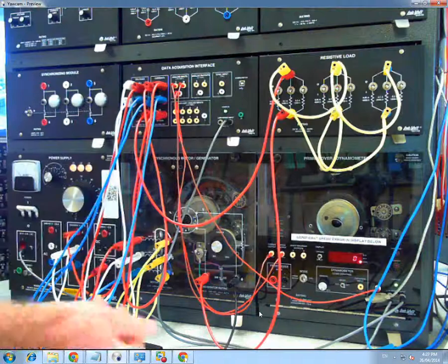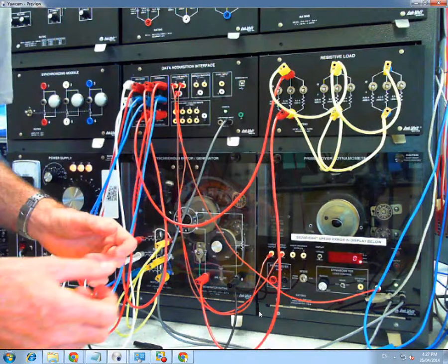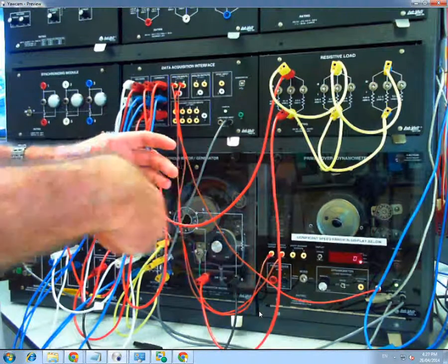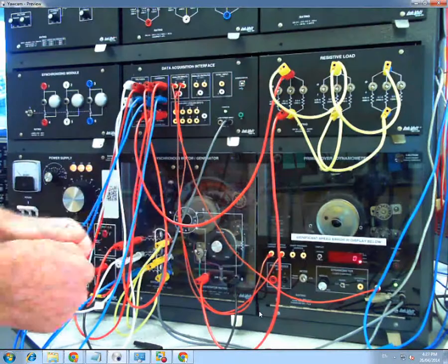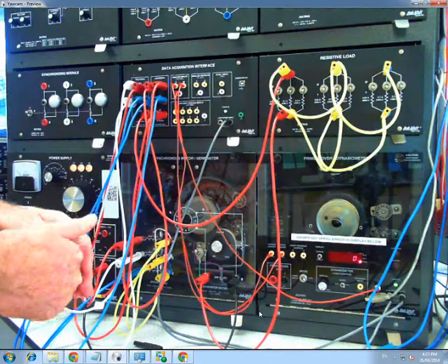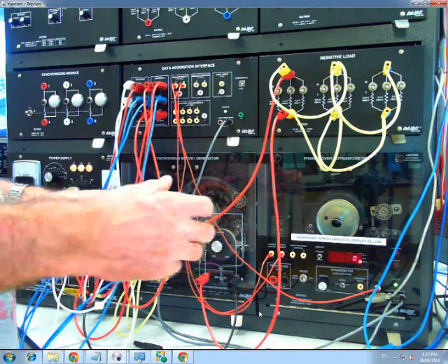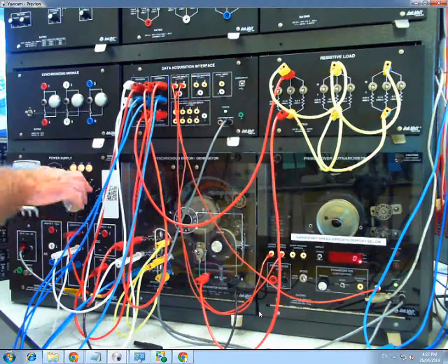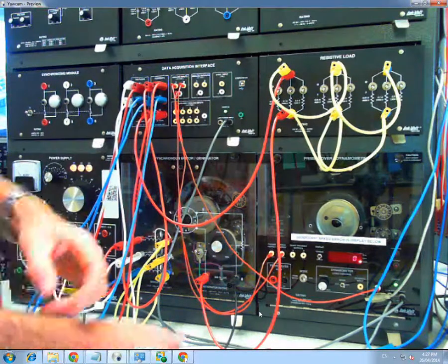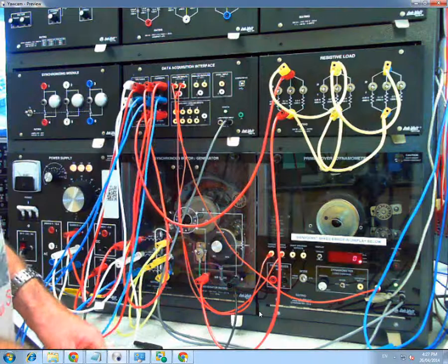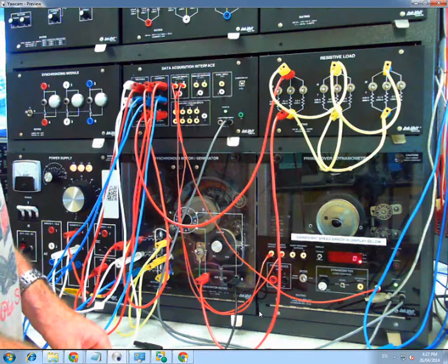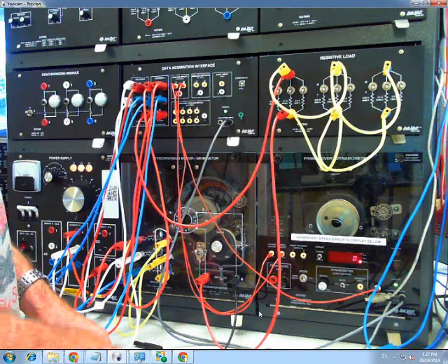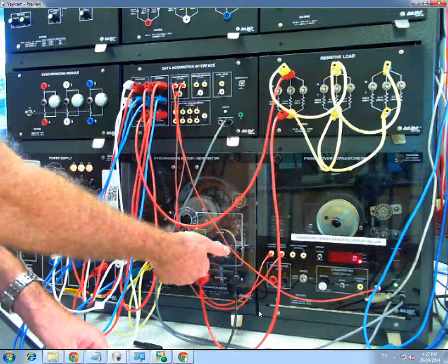inside the synchronous motor is a wound rotor component and a small squirrel cage like what you would see in an induction motor. The idea of the squirrel cage is that when you run it up to full power, the rotor runs at asynchronous speed, which is usually about 30 or 40 RPM slower than synchronous speed. And then it's ready for the excitation winding to be energized.